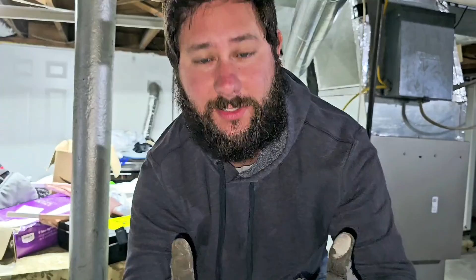Make sure you use the right coil cleaner. Not all coil cleaner is suitable for microchannel coils, so you want to make sure you use something like Tri-Pow'r HD. Link right here, get you some of this. This says here, ideal for microchannel coils. This is a detergent, degreaser, and deodorizer, so it's going to smell good.